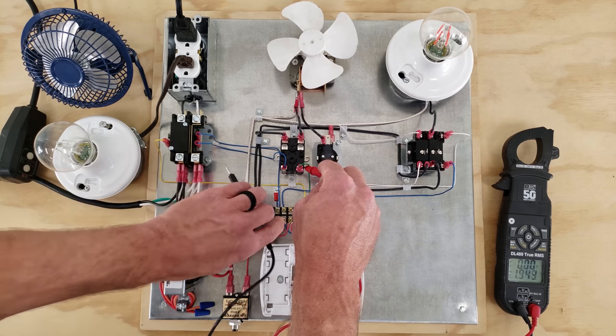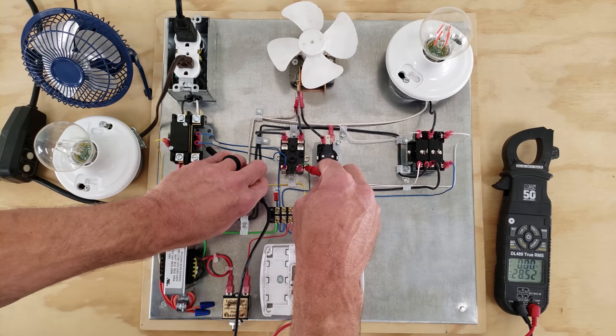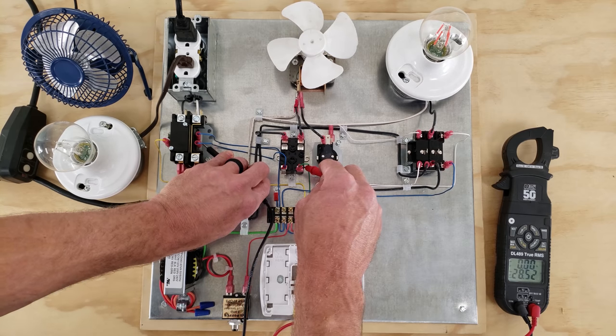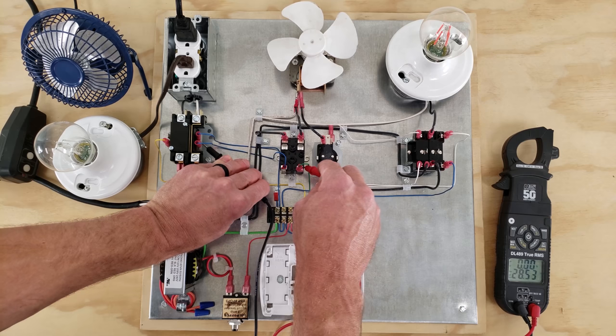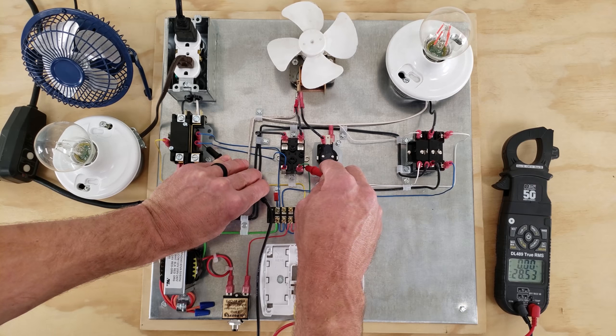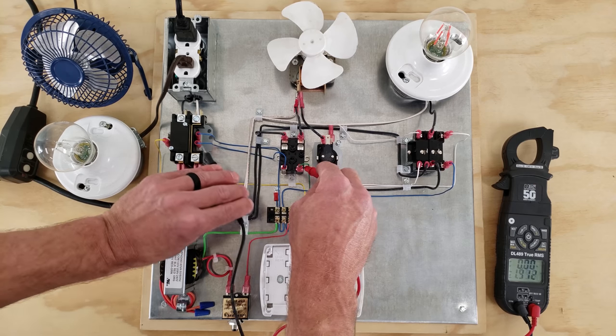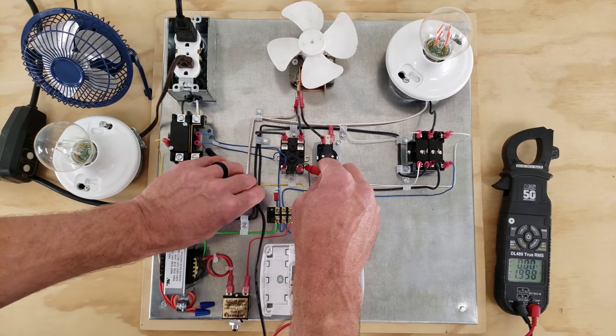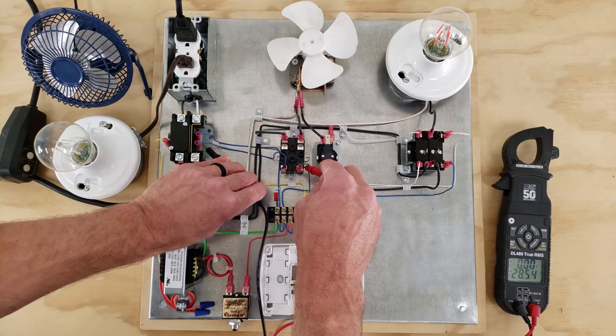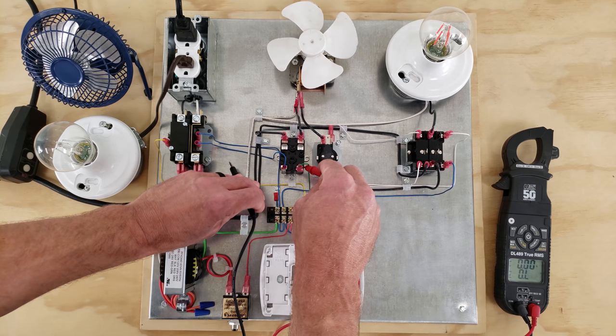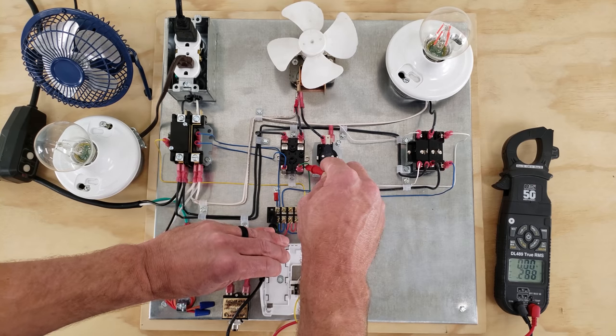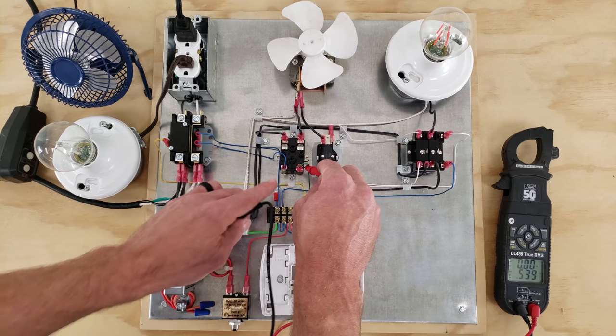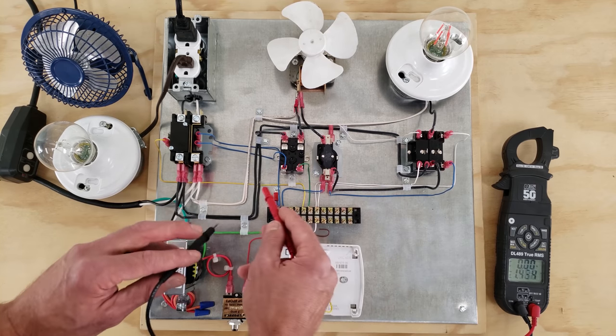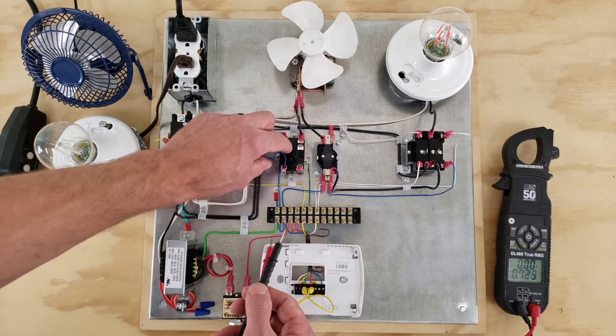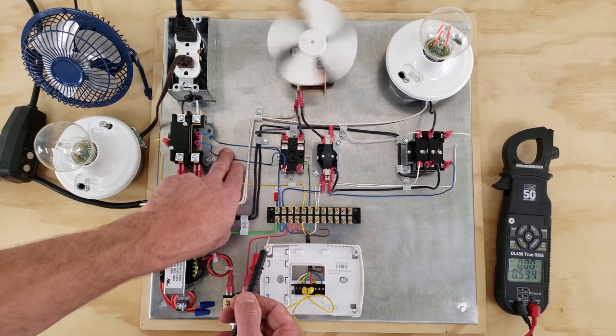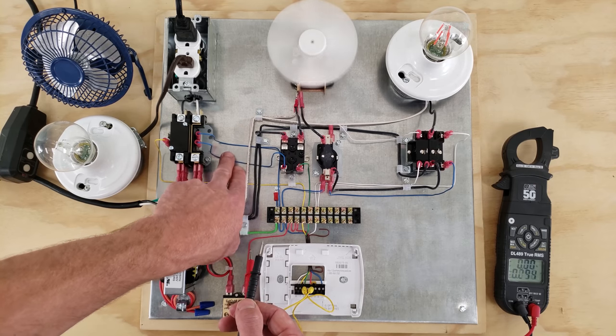And so let's check over at this common. So at this common, we have 29 volts still, so 28.5. So there must be some issue with this wire from here to here, because we do have our 29 volts anytime that we're touching ground or our common. So our issue is right here, in this wire right here. So let's just see, maybe it's an intermittent issue.